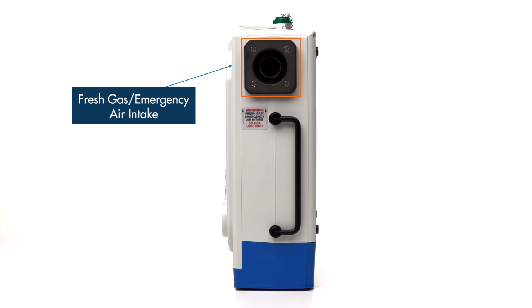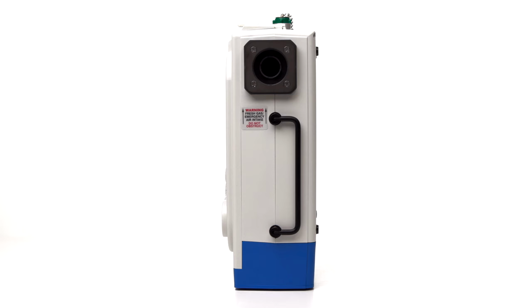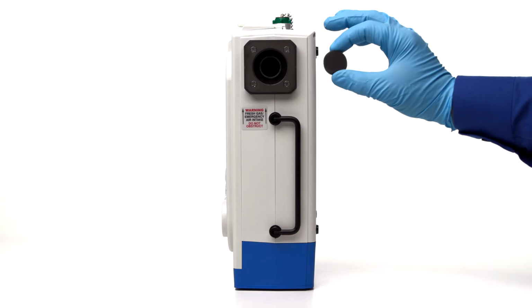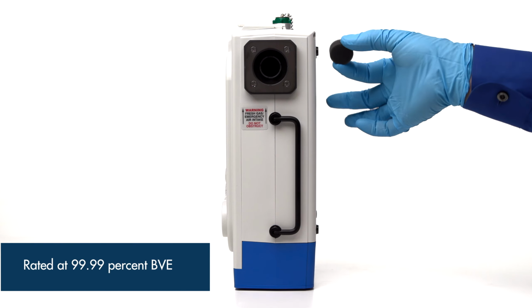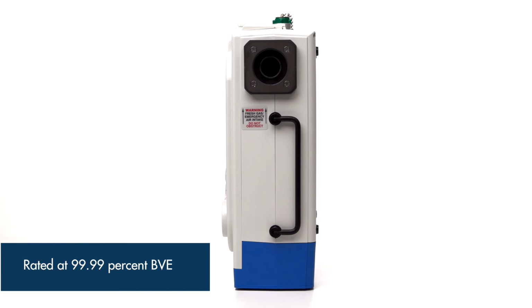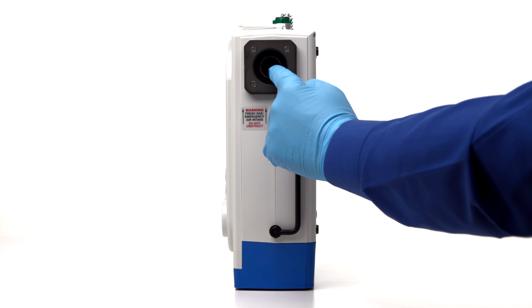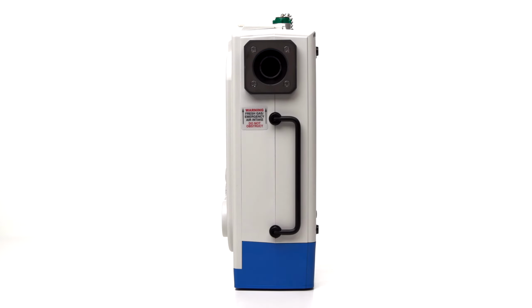At the top is the fresh gas intake port, which allows ambient air into the device's internal compressor. The Z Vent can operate either on room air or from an oxygen supply. Inside this port is the internal bacterial and viral filter, rated at 99.99% BVE. This filter should need replacing during the regular annual maintenance. In the event of a ventilator failure during operation, this port is also the emergency air intake, which acts as an anti-asphyxia valve that allows the patient to continue to breathe fresh air.